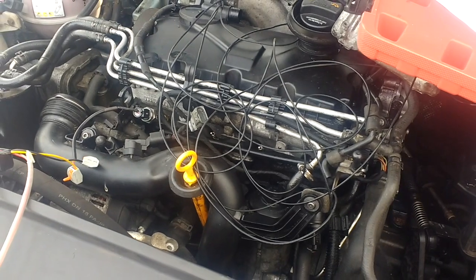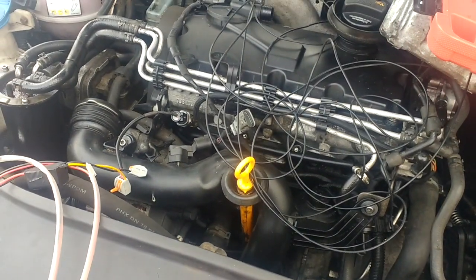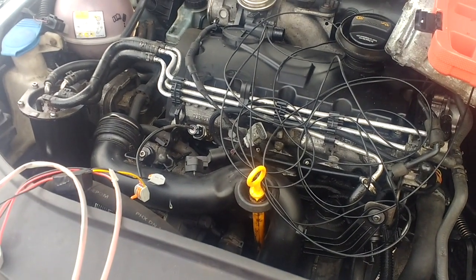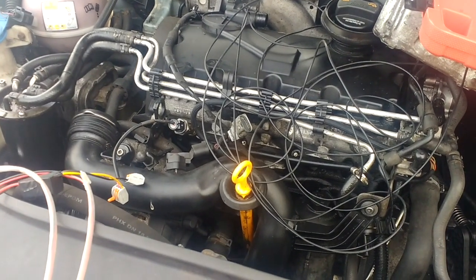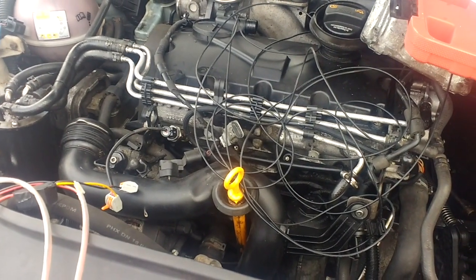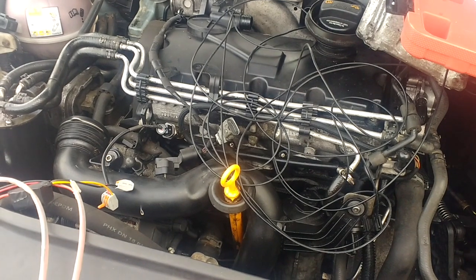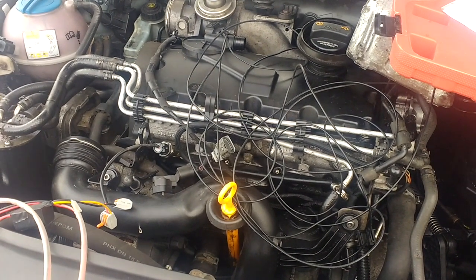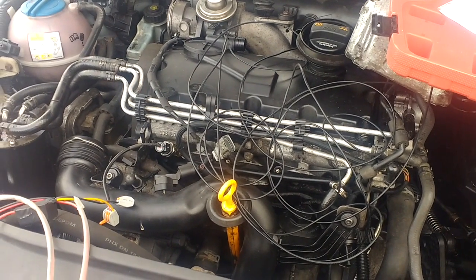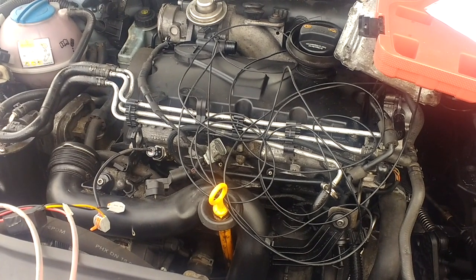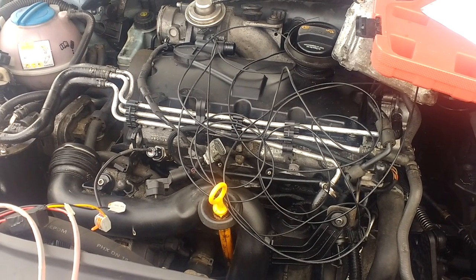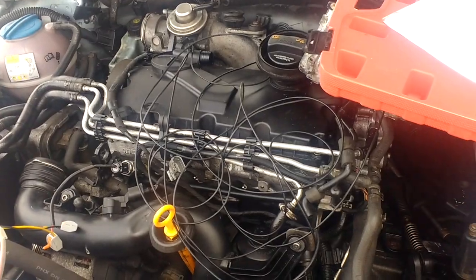A lot of you chimed in with ideas of what to test, but I thought I'd go with the one that Diagnosed Dan sent in about checking the injector against the current clamp. The problem is my current clamp doesn't go high enough, it's only 128 amps or so, it measures up to 250 amps and that's it off the scale.